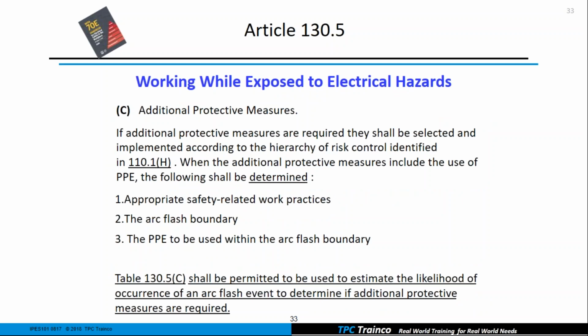Still in Article 130, working while exposed to electrical hazards, they tell us here if additional protective measures are required, they have to be selected and implemented according to the hierarchy of risk control. So again, eliminate, substitute, all those. When the additional protective measures include the use of PPE, so we got all the way down to number 6, then the following has to be determined: the appropriate work practices we're going to use, and we better know the arc flash boundary. The arc flash boundary would be determined either by the incident energy analysis method or the PPE category method. And then the PPE that we're going to use inside that arc flash boundary. And Table 130.5(C) can give us an indication of whether we are going to have to use these additional protective measures or not.